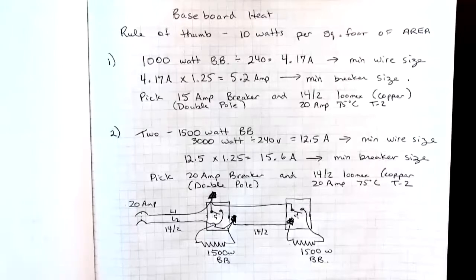So if your bedroom was 10 feet by 10 feet, it would be 100, multiply that by 10, you get a thousand watt baseboard heater is what you need in that room.